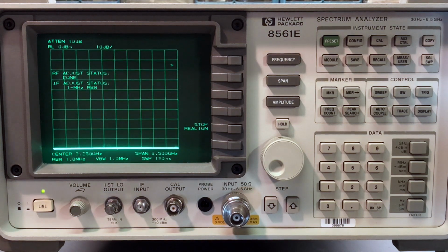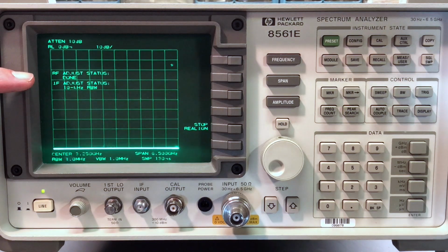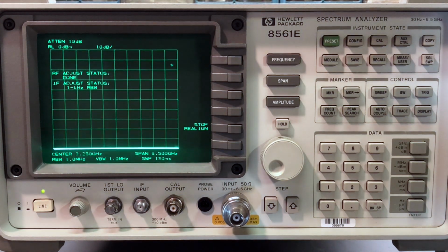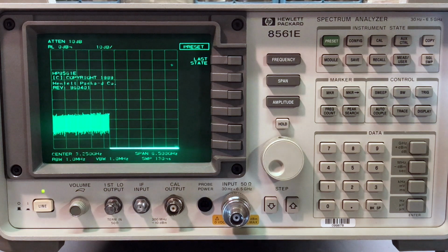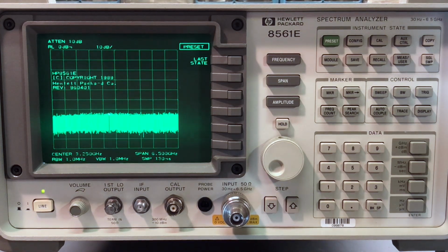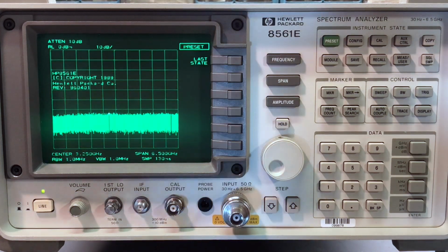We do see right here, it says RF adjust status, and that's done, and the IF adjust status is working through that. So we'll give it a moment. Pardon the flickering on the camera, that's just the refresh rate on that CRT not really playing nice with the camera. So it started up okay, no problems. There's no error codes, they would be indicated in this lower corner.